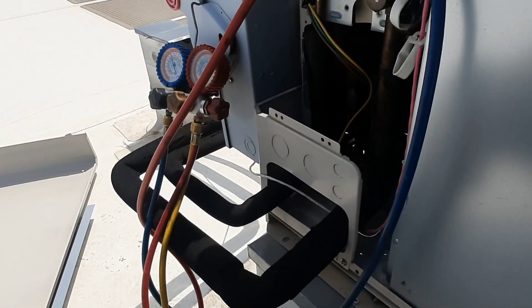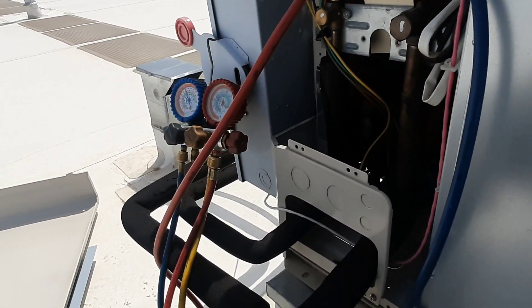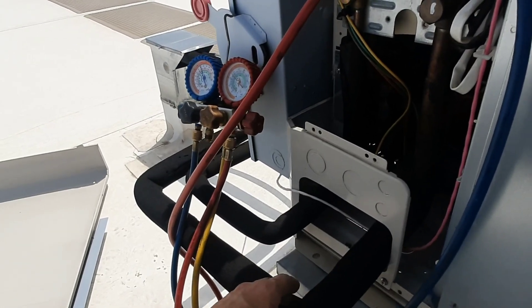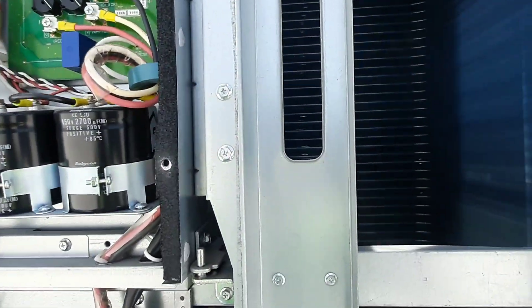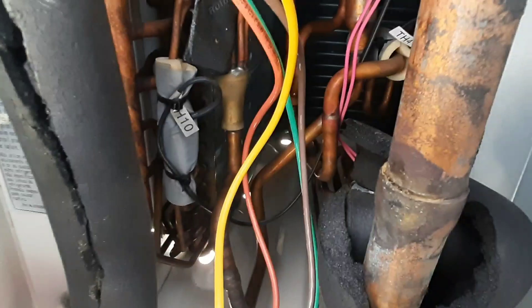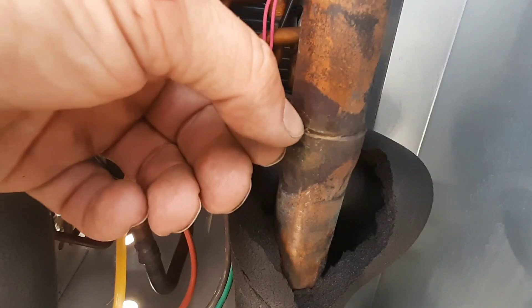The heads are about 15 feet or so above a drop ceiling in an office, so limited access. But I think I'd start with the header or distributor box — I don't know what you VRF guys call it — and all the actual connections. I don't even know how that is not leaking. Hell, that might be it right there. I would just expect to see some oil.